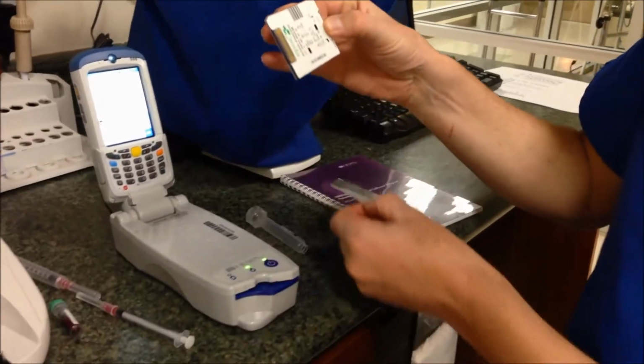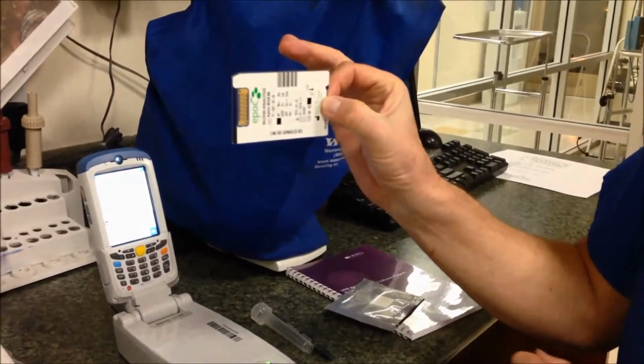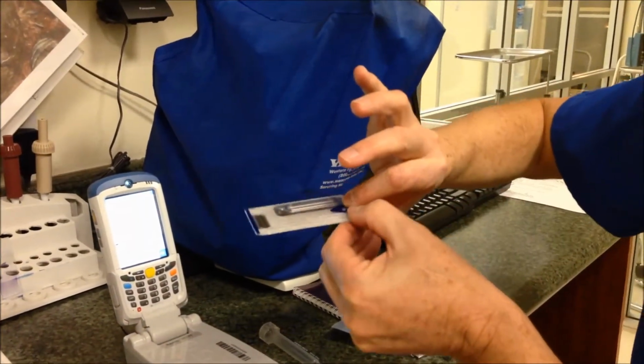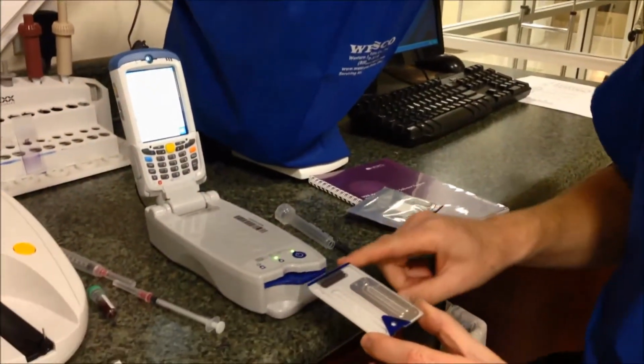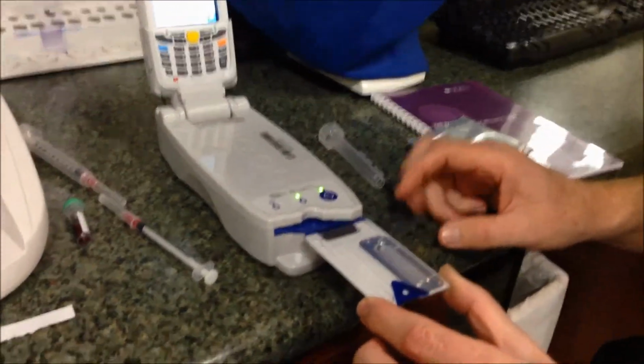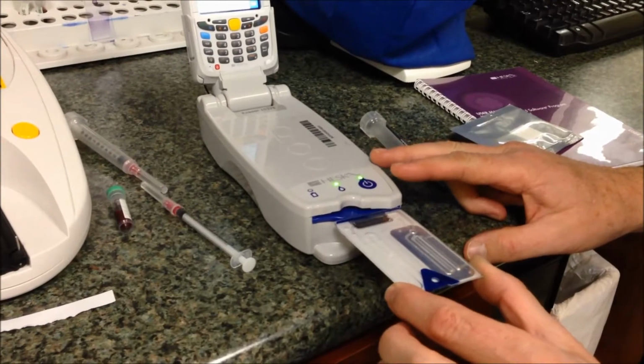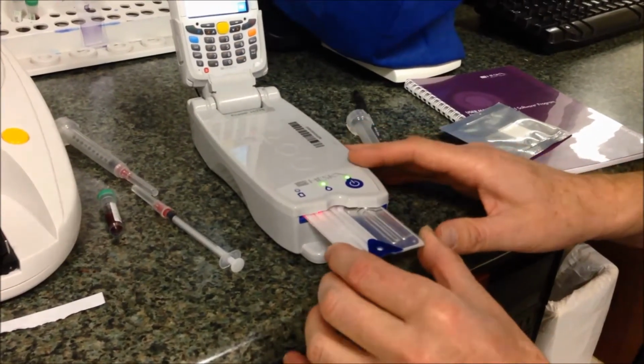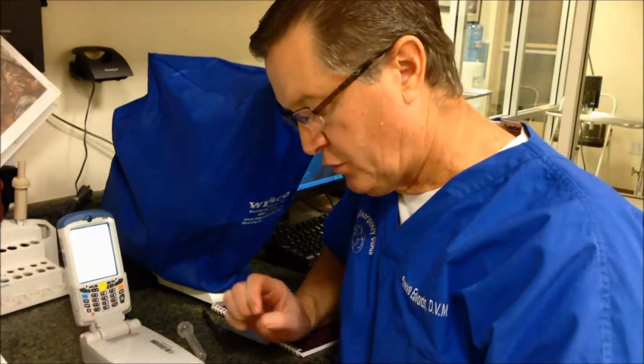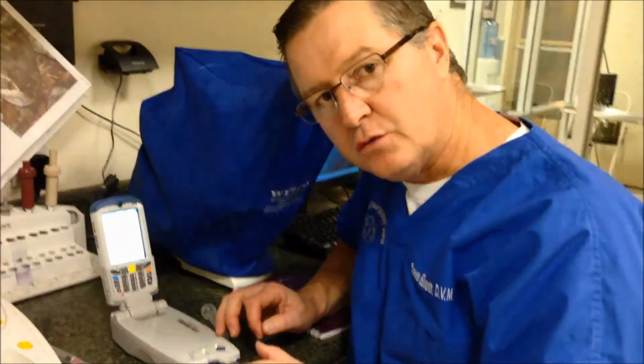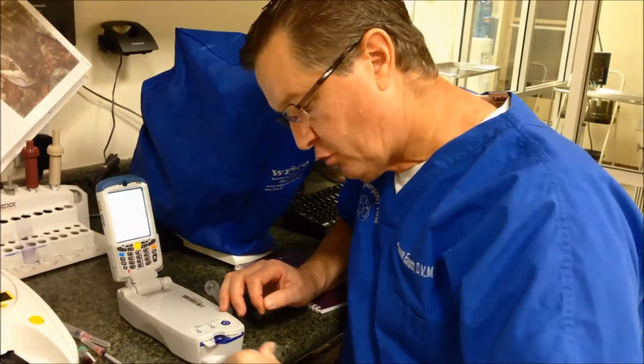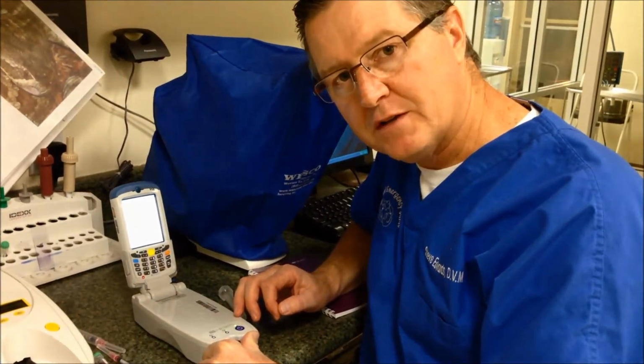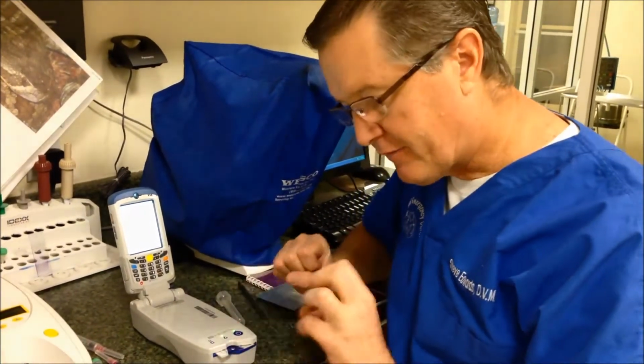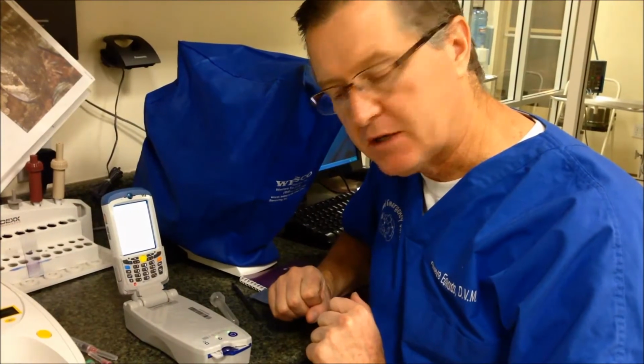The cartridge is very temperamental. You cannot touch the electrodes. You cannot lay the cartridge down on the table. It needs to be put right into the machine. There is a slot here at the foot of the machine that allows you to slide the cartridge in. And so you insert the card into the reader and push it with one smooth stroke all the way to the end. It kind of has a little bit of a grab feel to it at the end, and the machine makes a beep. Then, if you'll look here, it will show that it's in calibrating mode.